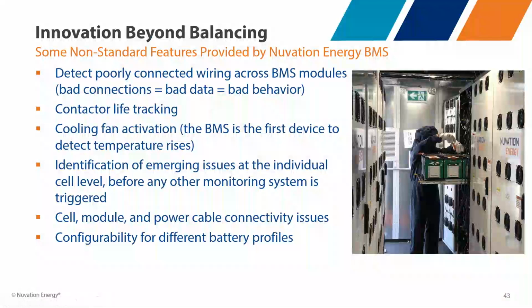And then we'll talk about some non-standard features provided by the Nuvation Energy battery management system. One of them is that we can detect poorly connected wiring across BMS modules. If you have a bad connection, you'll get bad data and possibly bad behavior. We call this open wire detection, and it's one of the features that we have in the Nuvation BMS. What it does is it uses the existing balancing wires and a proprietary software algorithm in order to compare the voltage drop of a cell when balancing versus not balancing. So there's no incremental hardware cost for this.